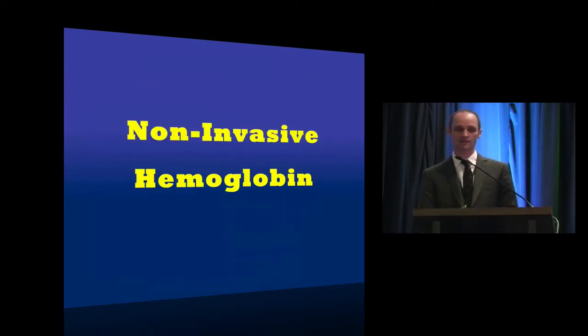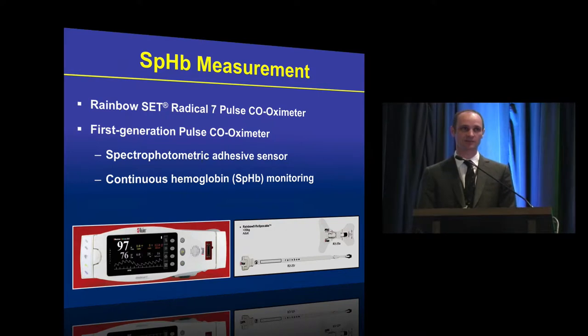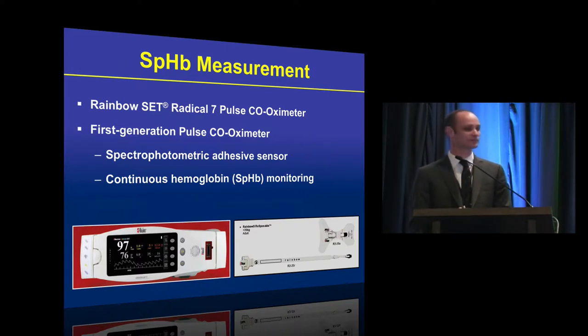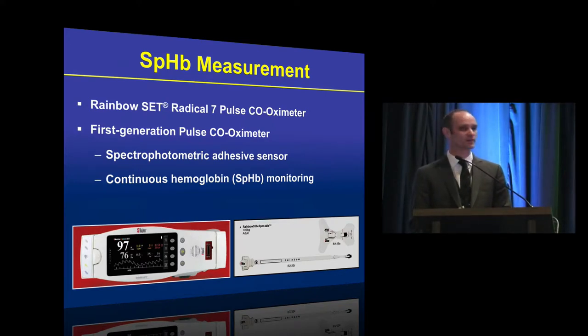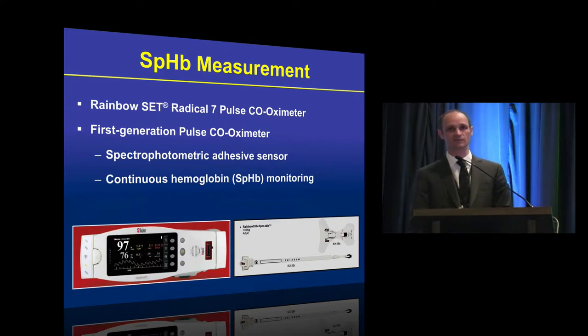The device that's attracted the most interest in the medical literature is this device manufactured by Masimo — the Rainbow Radical Seven pulse oximeter. What you're seeing here on this slide are pictures from the first generation of the device. On the right-hand side image, you can see the spectrophotometric adhesive sensor, and below that is an interconnect that connects the sensor to the base unit. The base unit converts the signal into an electrical signal, which then provides a hemoglobin concentration on the LCD.